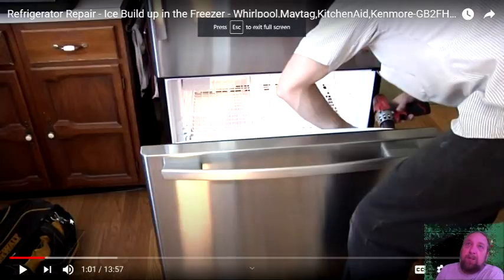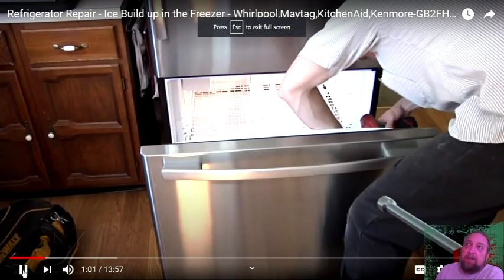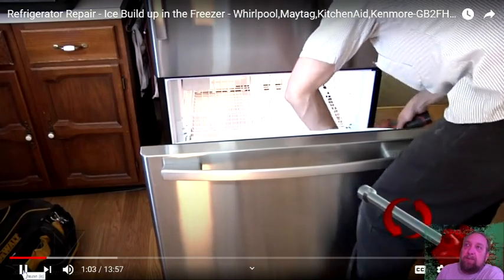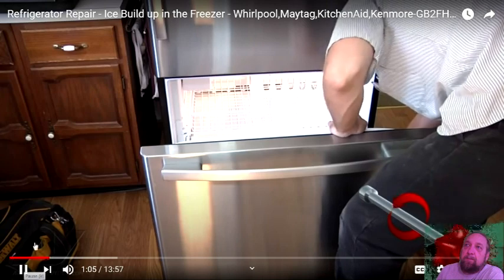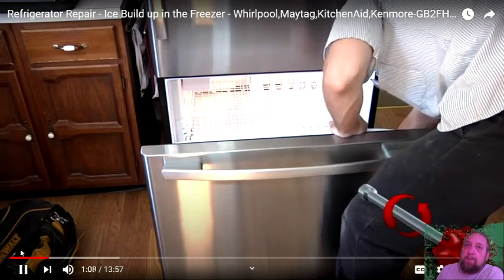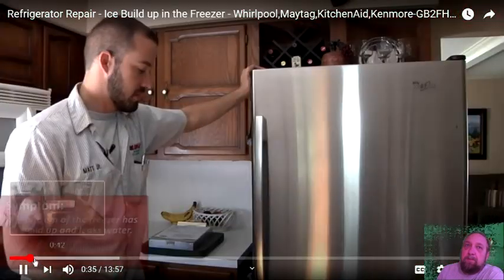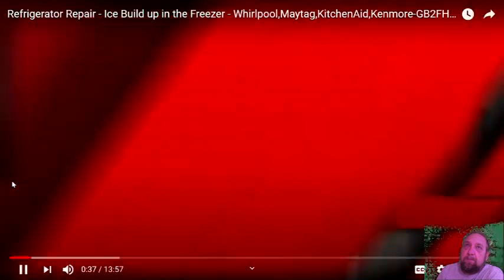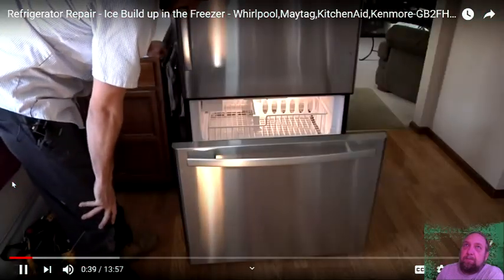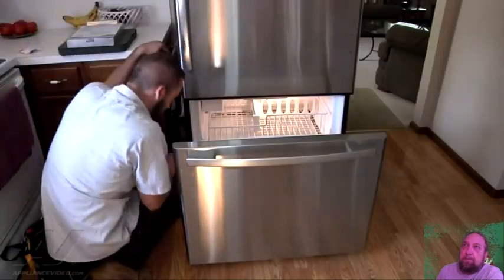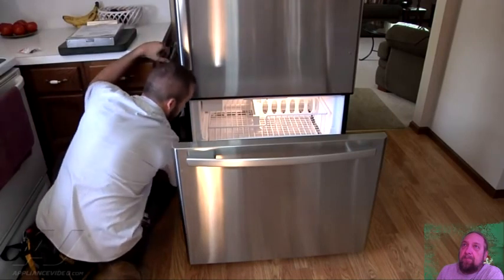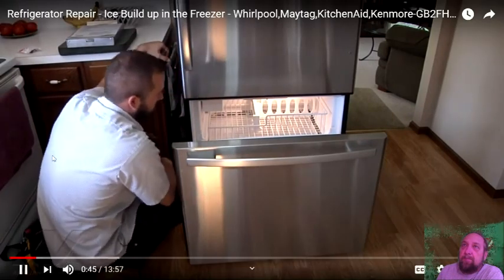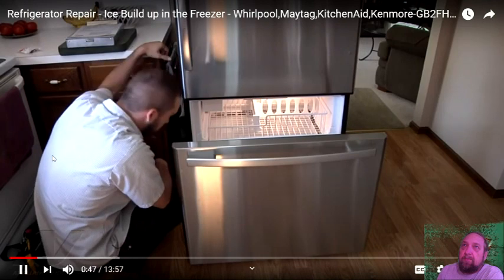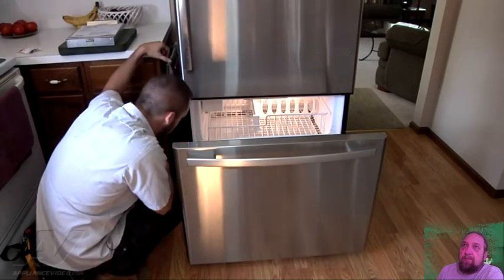I got one more video real quick. Go ahead and loosen the screws on the door here. Okay, let's open it up and see what we've got. All right, so we got a layer of ice down at the bottom of the freezer here, which is an indication that the drain line itself is going to be frozen.